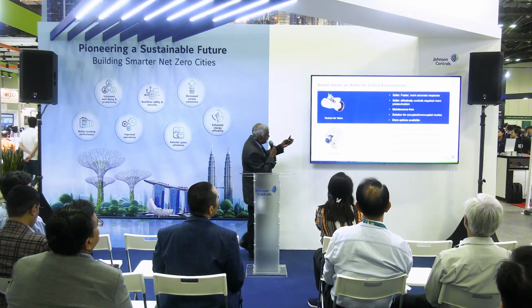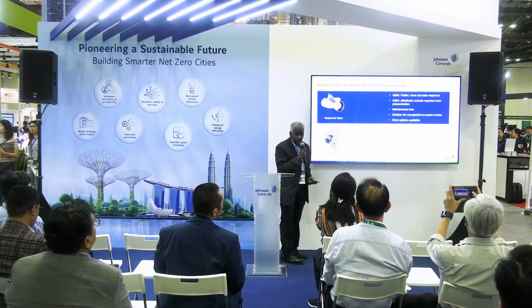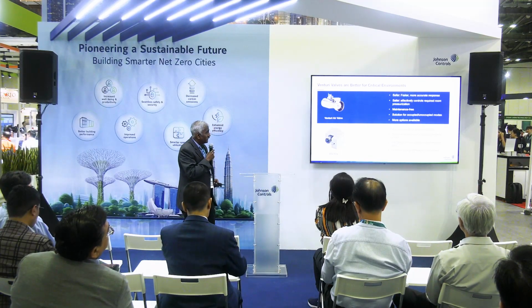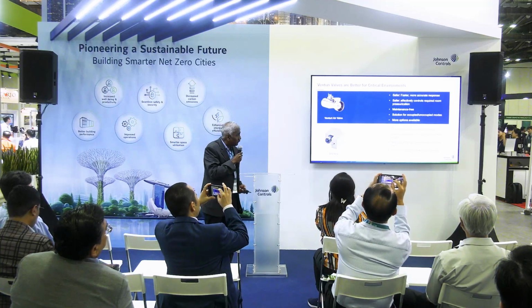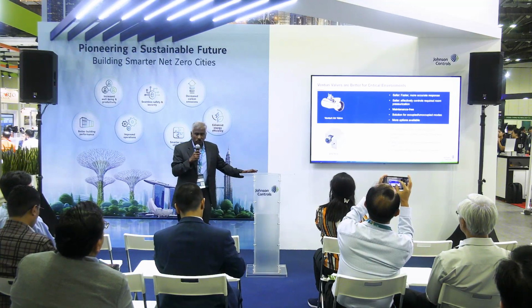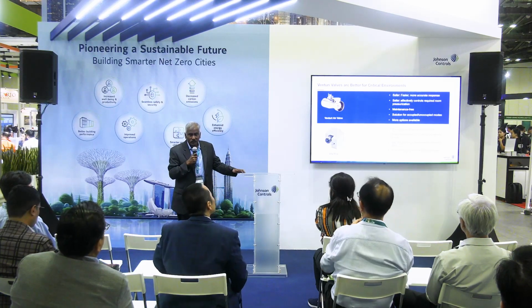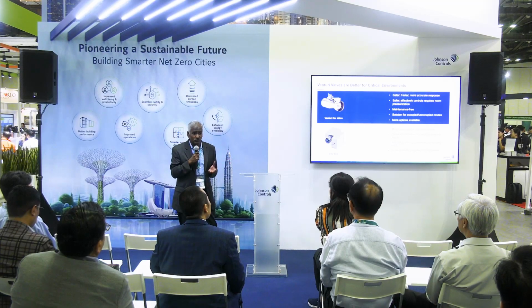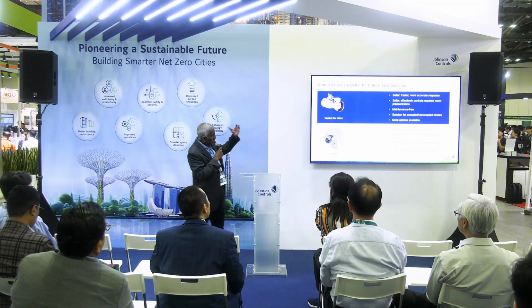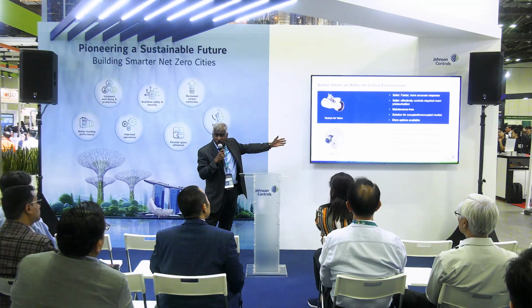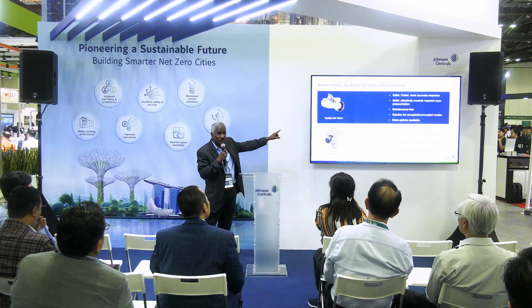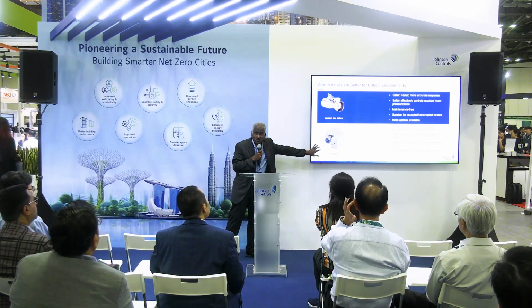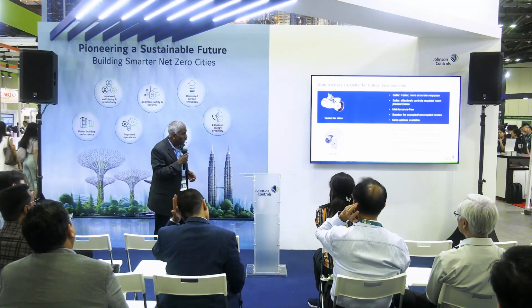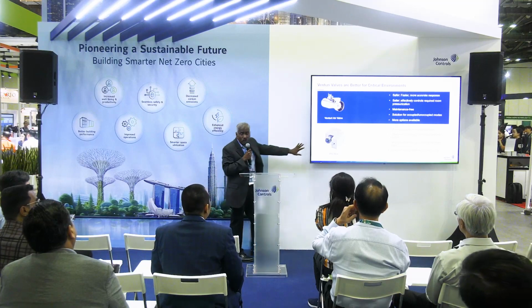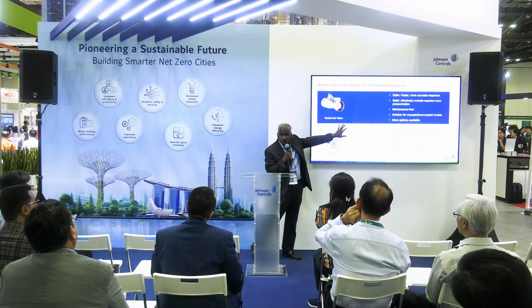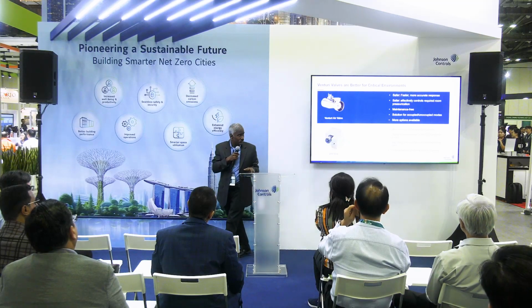So coming back to the summary: the venturi air valve is safer, with faster, more accurate response and efficient control. It's maintenance free, and a solution for occupied and unoccupied modes. I forgot to mention this: we always talk about net zero and how to reduce energy. When you're not using an OT for, let's say, 30 or 40 minutes, with a venturi valve you can switch it off or go to unoccupied mode. And when you put it back to occupied mode, it goes back to control very, very fast. But if you're using a VAV box, it takes 30 to 40 minutes, so most places that use VAV boxes just keep it on. Imagine you have 10 or 15 OT rooms in a big hospital. There's a lot of energy saving that can be conserved.